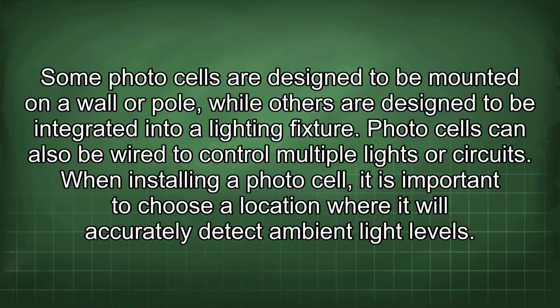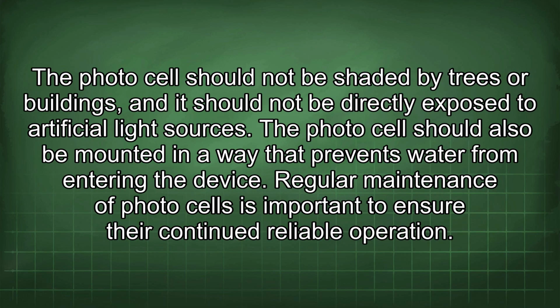Some photocells are designed to be mounted on a wall or pole, while others are designed to be integrated into a lighting fixture. Photocells can also be wired to control multiple lights or circuits. When installing a photocell, it is important to choose a location where it will accurately detect ambient light levels. The photocell should not be shaded by trees or buildings, and it should not be directly exposed to artificial light sources. The photocell should also be mounted in a way that prevents water from entering the device.